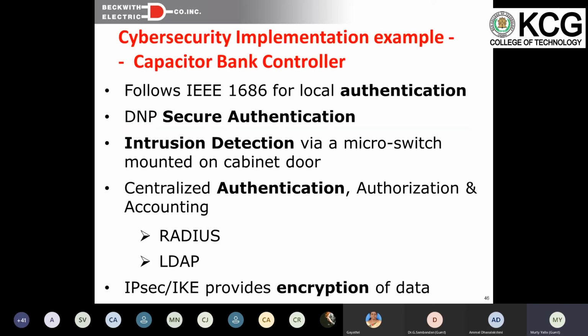I picked one IED, a controller that controls capacitor banks. A similar control might be controlling a tap changer, or a voltage regulator, or a recloser, or maybe providing protection for a feeder. It doesn't matter what the device is. Any of those devices have to have security mechanisms. Some of the basic mechanisms exist because, way back 8 years ago, a utility that feeds some of the critical governmental infrastructure in the United States came to us and said, we feed the most sensitive installations and we need a lot of cybersecurity features in your product. So we spent 14 months and more than $1 million designing.